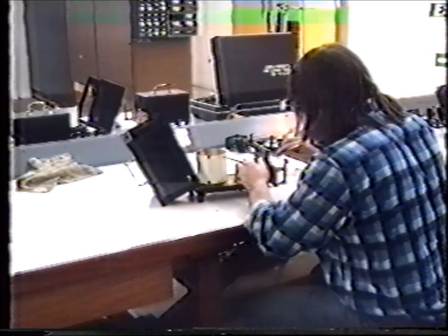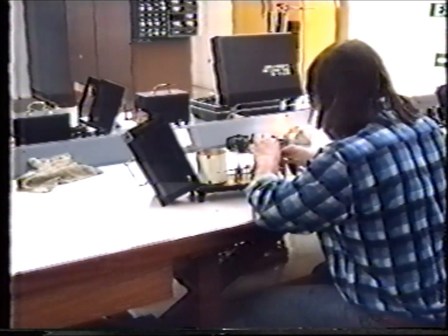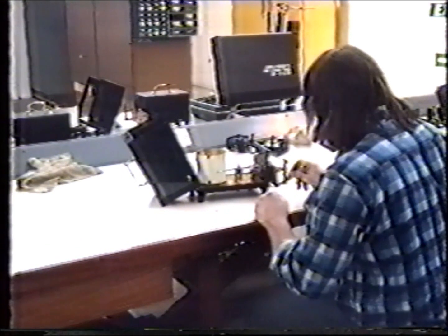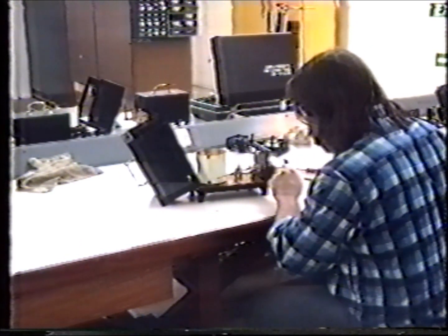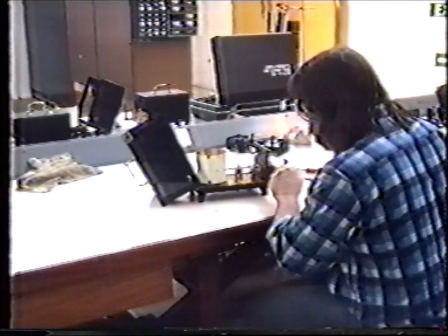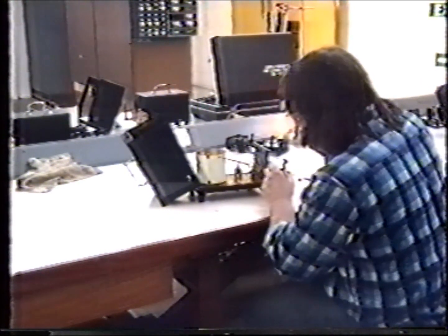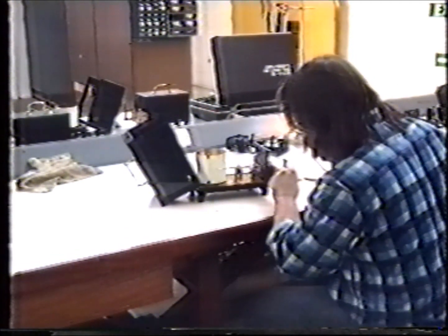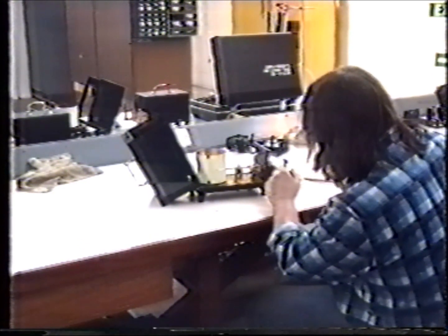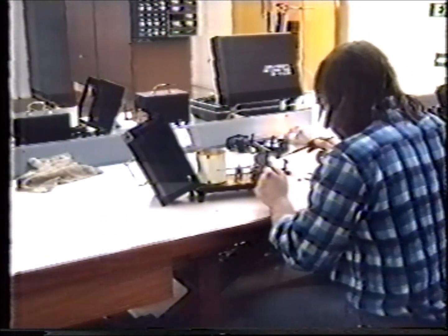In the Quality Assurance Laboratory, the refurbished units rarely work correctly at first, and so after first fitting the clock and drum, the hair is attached to the pen arm mechanism and the span control checked. The deft use of a small instrument is useful for these setting up procedures. Distilled water is applied to the hair and a check made at 100% relative humidity.